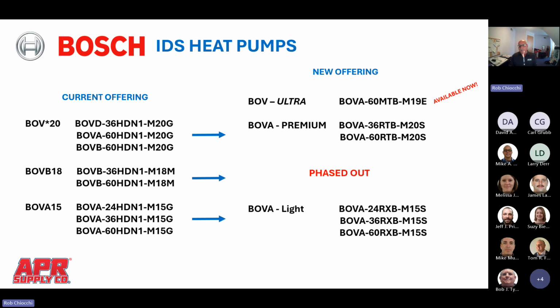Part of that new offering, and I'm proud to say we already have in stock and available for purchase today, is the new Bosch BOV Ultra Cold Weather Climate Heat Pump. This heat pump is rated at 19 SEER2, full capacity down to 5-degree ambient outdoor temperature, and is rated Energy Star Cold Climate Heat Pump. This is available today in the 5-ton with a 4 or 5-ton air handler in the R454B platform.